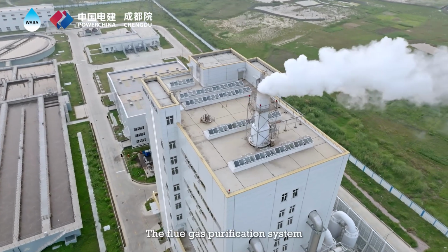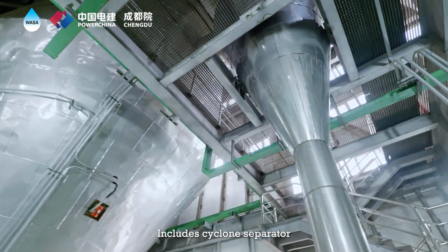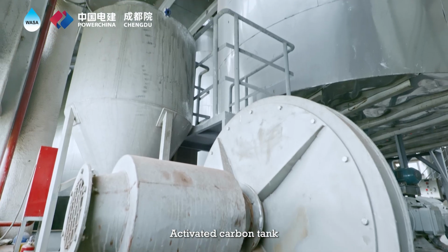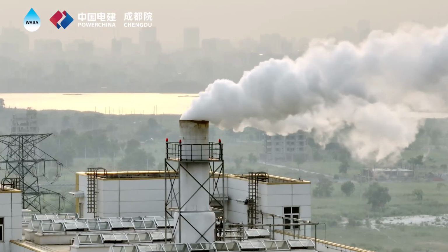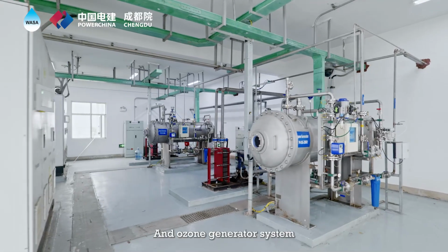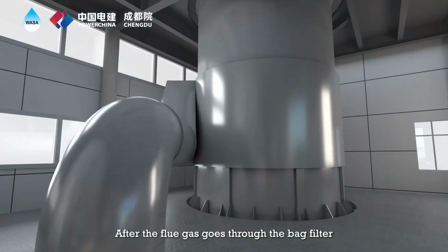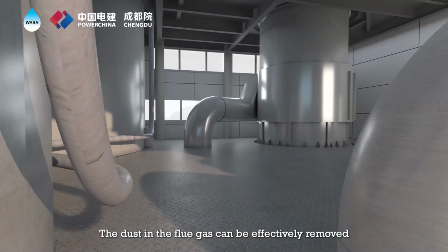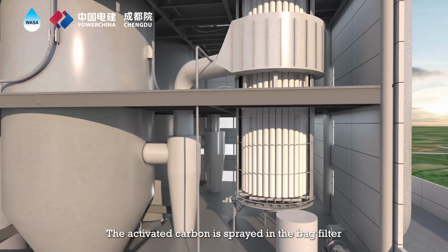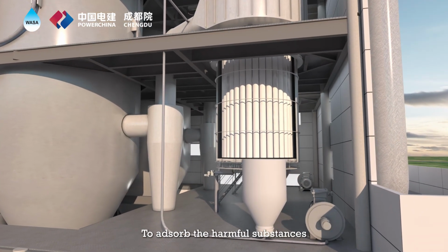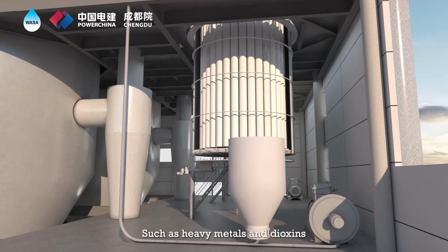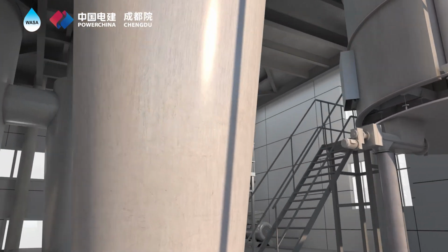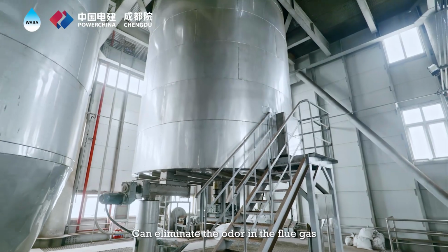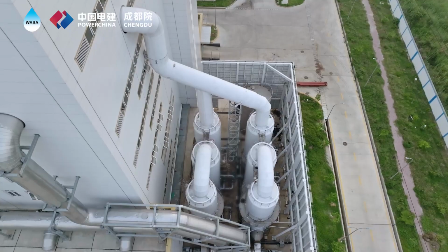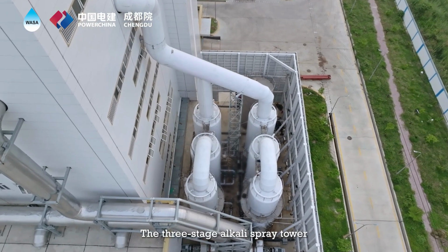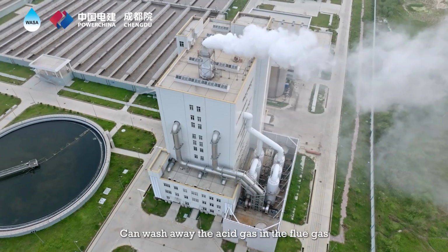The flue gas purification system includes a cyclone separator, bag filter, activated carbon tank, spray tower, chimney, and ozone generator system. After the flue gas goes through the bag filter, the dust in the flue gas can be effectively removed. The activated carbon is sprayed in the bag filter to absorb harmful substances such as heavy metals and dioxins, and the ozone generator system can eliminate the odor in the flue gas. The 3-stage alkali spray tower can wash away the acid gas in the flue gas.